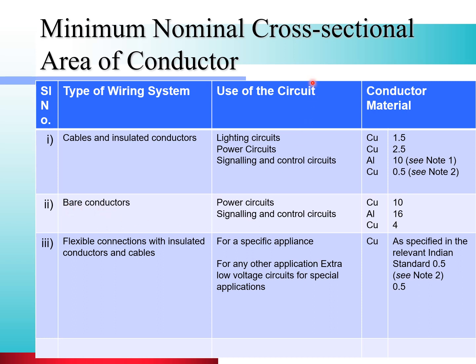For bare conductors used in power circuits, copper material requires 10 mm². For signaling and control circuits, aluminum requires 16 mm², and copper requires 4 mm². For flexible connections with insulated conductors and cables: for specific appliances using copper, the area is 0.5 mm². For extra low voltage circuits and special applications, copper material requires 0.5 mm².